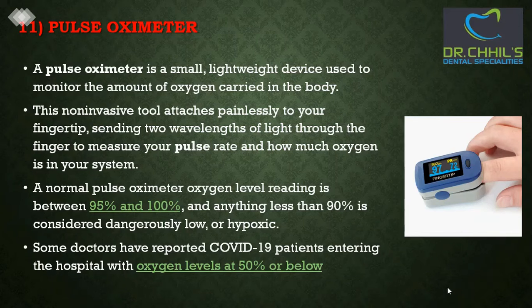Pulse oximeter. A pulse oximeter is a small, lightweight device used to monitor the amount of oxygen carried in the body. This non-invasive tool attaches painlessly to your fingertip, sending two wavelengths of light through the finger to measure your pulse rate and how much oxygen is in your system. A normal pulse oximeter oxygen level reading is between 95% and 100%, and anything less than 90% is considered dangerously low or hypoxic. Some doctors have reported COVID-19 patients entering the hospital with oxygen levels at 50% or below.